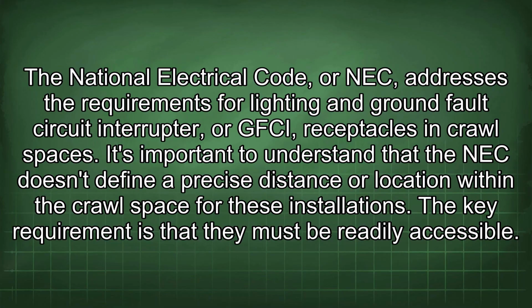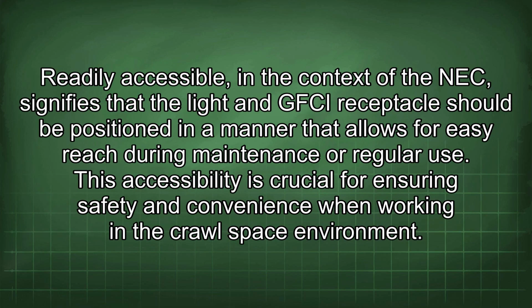The National Electrical Code, or NEC, addresses the requirements for lighting and ground fault circuit interrupter, or GFCI, receptacles in crawl spaces. It's important to understand that the NEC doesn't define a precise distance or location within the crawl space for these installations. The key requirement is that they must be readily accessible. Readily accessible, in the context of the NEC, signifies that the light and GFCI receptacle should be positioned in a manner that allows for easy reach during maintenance or regular use. This accessibility is crucial for ensuring safety and convenience when working in the crawlspace environment.